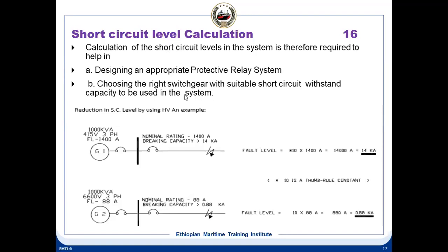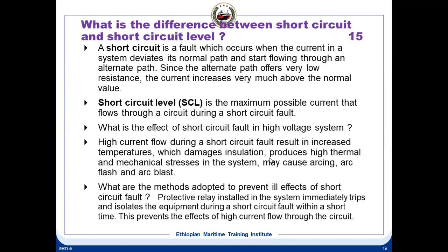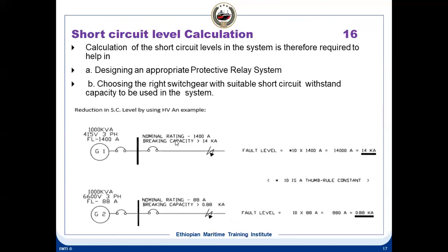So another advantage is this short circuit level is reduced. I told you what short circuit level is: the maximum possible current that flows through a circuit during a short circuit fault. This is reduced in case of high voltage systems. In a low voltage system, the short circuit level current is very high, so you need to have higher rating breakers. Whereas in case of high voltage, since the short circuit level is reduced, the breaker capacity can be reduced, the cost can be reduced, space can be reduced. All these are further advantages.